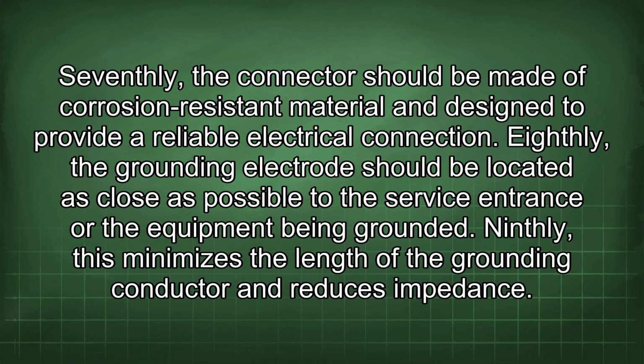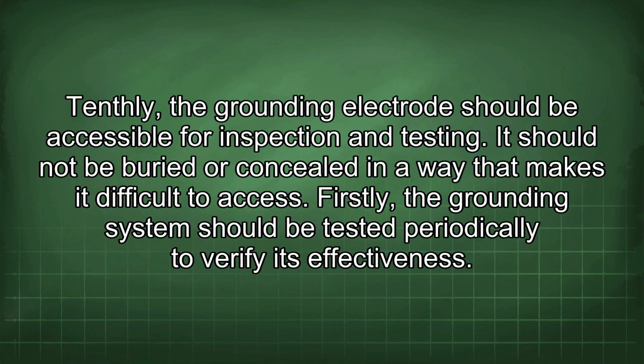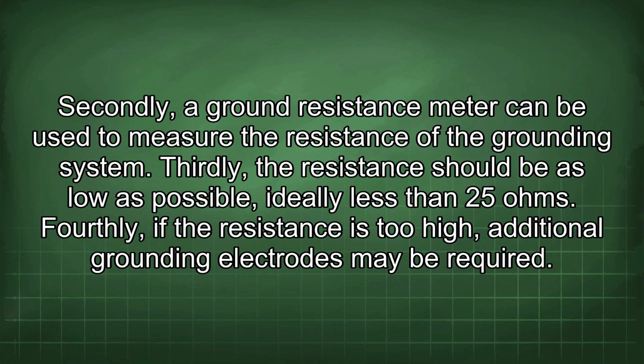Seventhly, the connector should be made of corrosion-resistant material and designed to provide a reliable electrical connection. Eighthly, the grounding electrode should be located as close as possible to the service entrance or the equipment being grounded. Ninthly, this minimizes the length of the grounding conductor and reduces impedance. Tenthly, the grounding electrode should be accessible for inspection and testing. It should not be buried or concealed in a way that makes it difficult to access. Firstly, the grounding system should be tested periodically to verify its effectiveness. Secondly, a ground resistance meter can be used to measure the resistance of the grounding system.